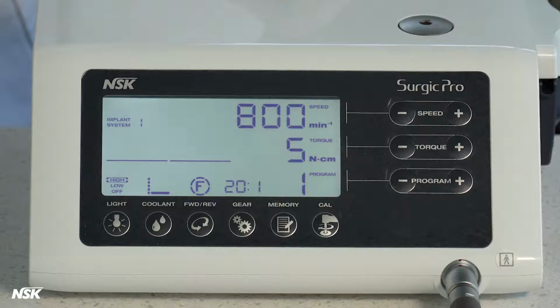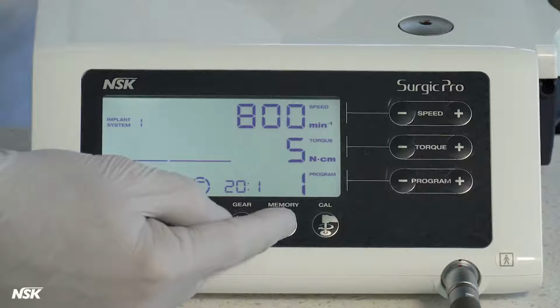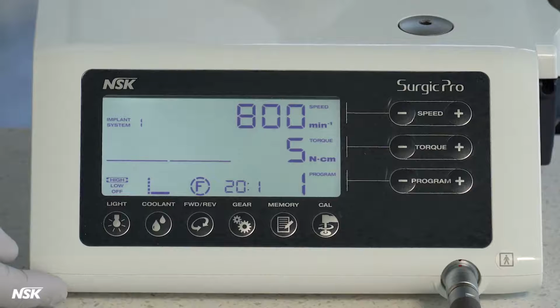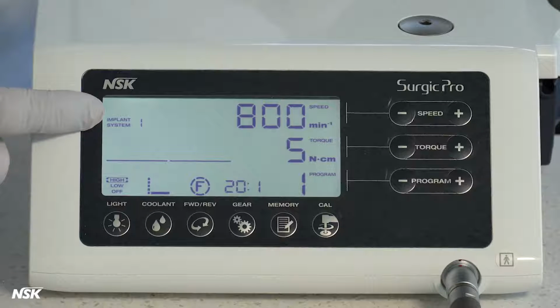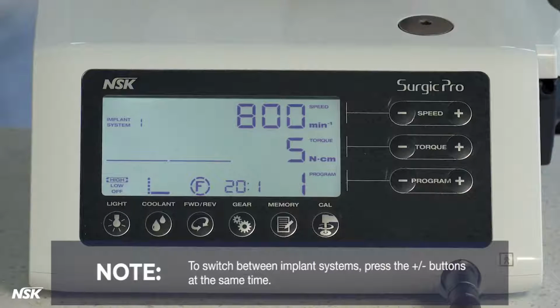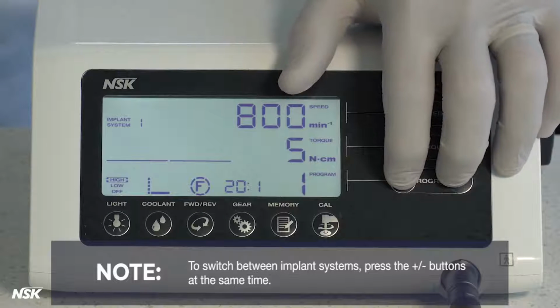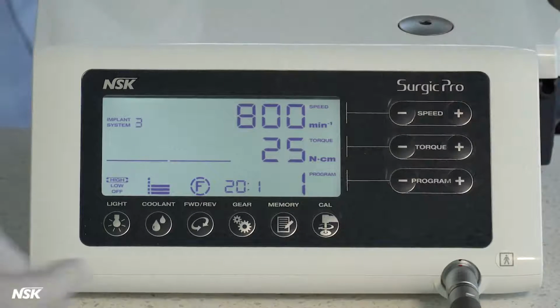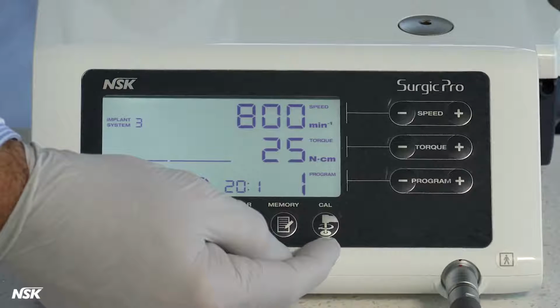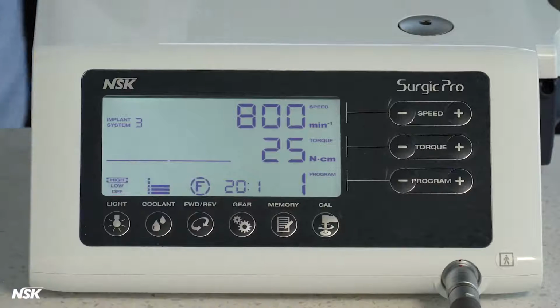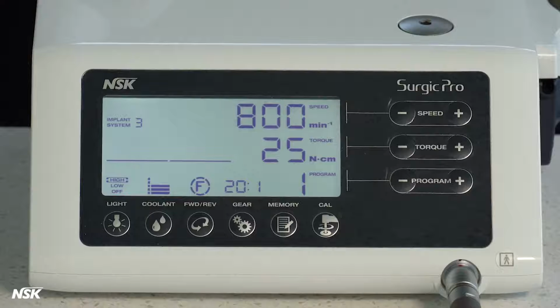Memory button is used to store the parameters of a custom setting in a program. After choosing the proper speed, torque, gear ratio, forward or reverse, coolant flow, simply press the memory button for 2 seconds until you hear a beep to store the settings. You can store up to 8 programs for 8 different implant systems. Note: to switch between implant systems, press the plus or minus buttons at the same time. The Cal button is used to calibrate a new attachment. There will be more on this in the calibration section later in this video.